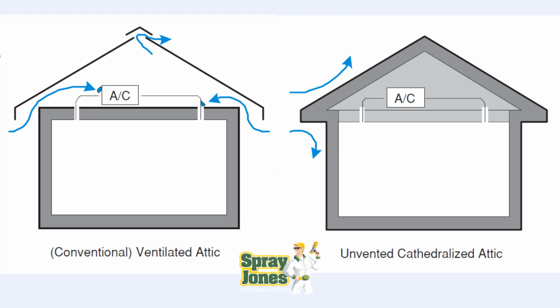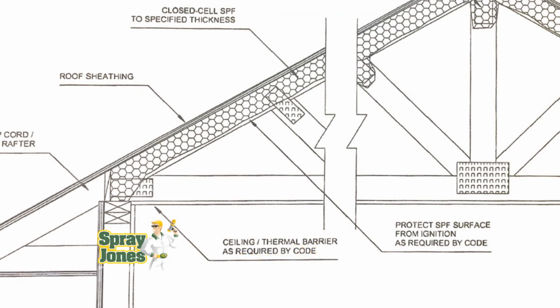If you are putting mechanical equipment, the furnace, the water heater, the air conditioner into the attic, there's going to be a lot of code jurisdictions, including the one we have here in Canada, that are going to require a thermal barrier over top of the spray polyurethane foam. If that's the case, there's two ways to beat it. You either pony up the cash and spray the thermal barrier on the spray foam, at which point you've just paid for all this foam to go on. Now you've got to pay for all this thermal barrier to go on. Very cost prohibitive, very, very negative.